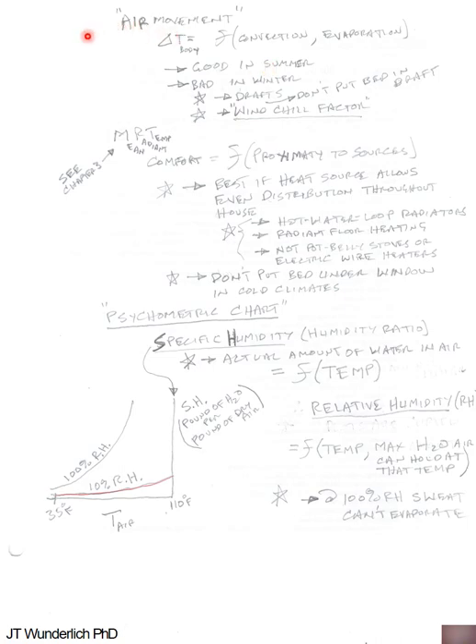So now some design considerations. Air movement. The change in the temperature in your body is a function of convection and conduction evaporation. And it's good in the summer. Air movement cools you off, but bad in the winter. Wind chill factor and the drafts in buildings. Don't put your bed under a window, for example. Mean radiant temperature. We talked about this for comfort in Chapter 3. It has to do with proximity to sources. It's best if the heat is evenly distributed. Hot water loop radiators rather than electric kind of heaters. Radiant floors. Not a pot belly stove or electric wire heaters, which are intense point sources. It's better to evenly distribute.